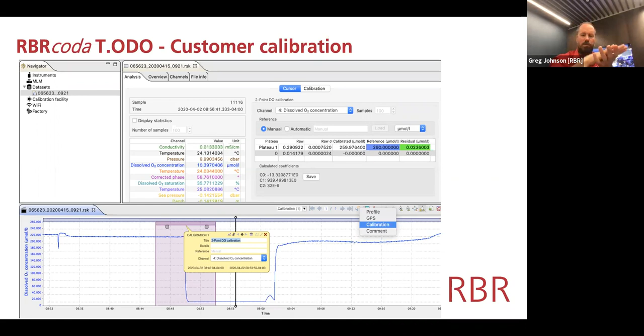and that will give you a 0% level. When you look at that data in Ruskin, you'll have those 2 levels, and you simply indicate which level is used during which part of that deployment. And the Ruskin software will then calibrate those coefficients for you for the 2-point calibration, which is laid on top of that 49-point calibration.